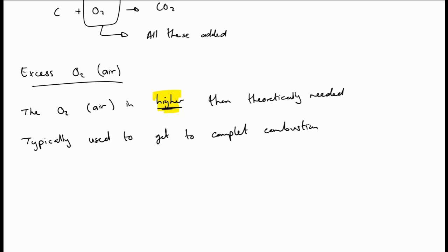Typically we do this to get complete combustion. As if we use the exact amount of oxygen, we have a very good chance of not combusting all the carbon. So excess air, excess oxygen, the higher amount of oxygen fed to the system to try and get to complete combustion. Higher than the theoretical value needed.